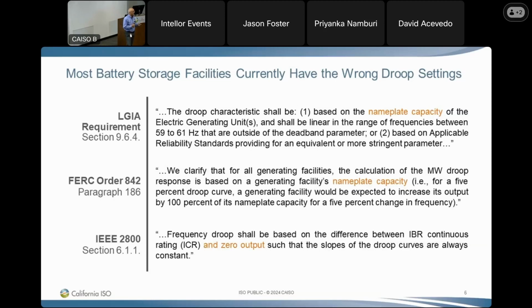If you look at FERC Order 842, and our LGIA requirements, it's based on nameplate capacity — and those are not necessarily the same. Your nameplate is not necessarily 0 to Pmax, which is what IEEE 2800 says your droop setting should be. Again, if you're not in the weeds, a lot of this may not make sense, but if you're involved with projects, you've got to make sure your projects have the correct droop settings on them.